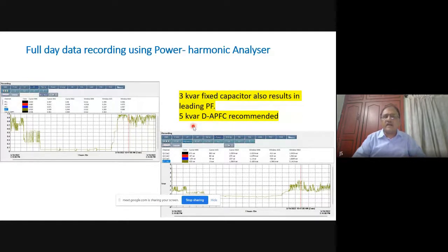So a 5 kVAR detuned APFC was recommended here. We are in the process of installing this and ensuring that the little bit of harmonic that is there in the system does not unnecessarily create a problem for the power factor. And you will be surprised to know that I was able to find 5 numbers of 1 kVAR with equivalent reactor. There is a manufacturer in Bangalore who provided the reactor. So we put a detuned APFC of 5 kVAR, simple LT industry, but this will give them relief from headache.